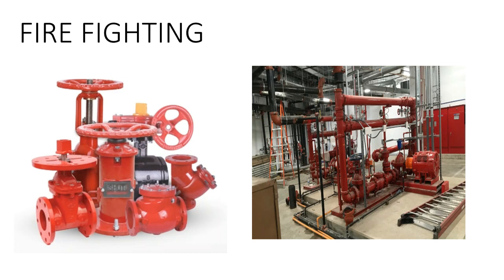These three pumps will be connected with the control panel, and this control panel will give a signal to the pumps based on fire alarm initiating devices like heat detectors, smoke detectors, or manual call points. If any of these detectors or points are initiated, they will give a signal to the fire alarm control panel. Then the fire alarm control panel will give a signal to the pump control panel. The pump control panel will start the pumps. First the jockey pump will start, then the electrical pump, then the diesel pump.